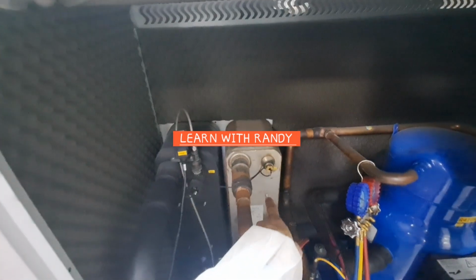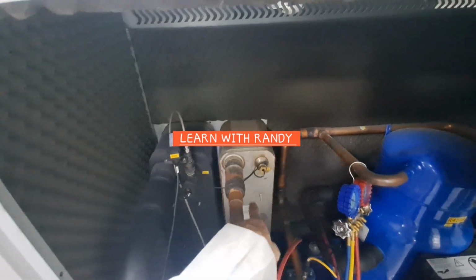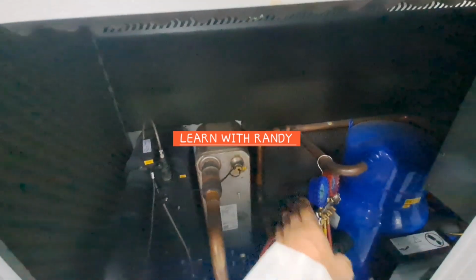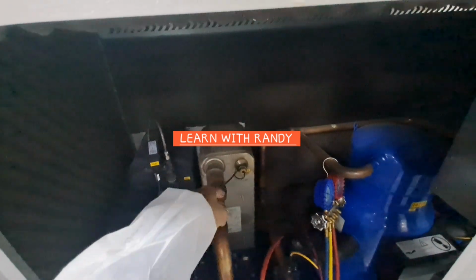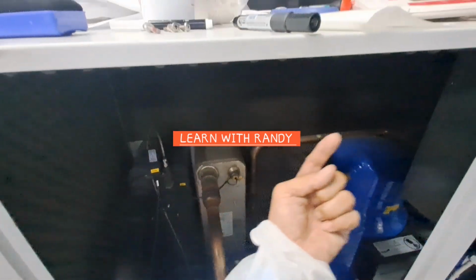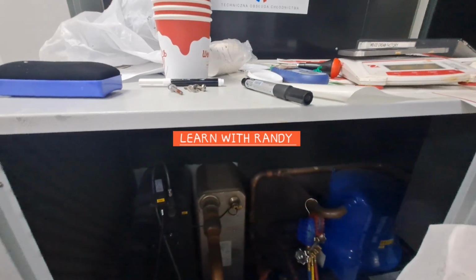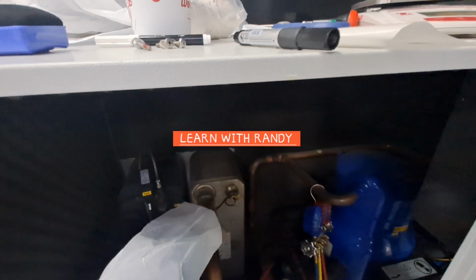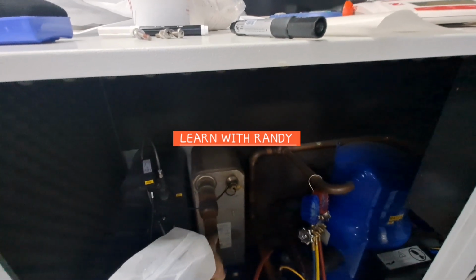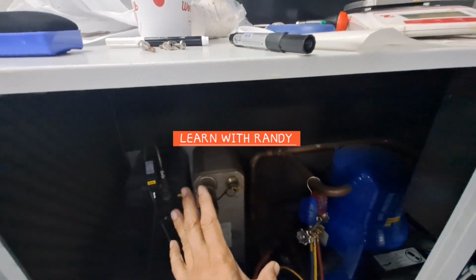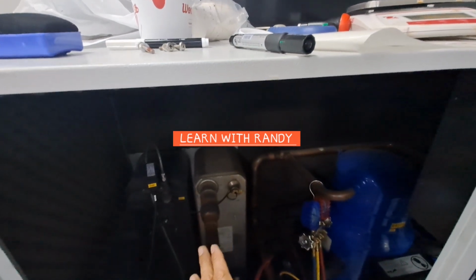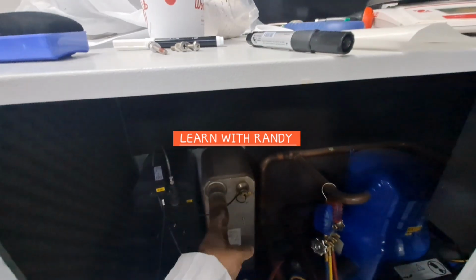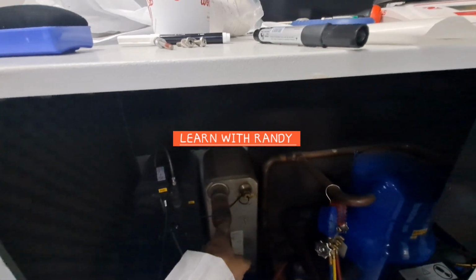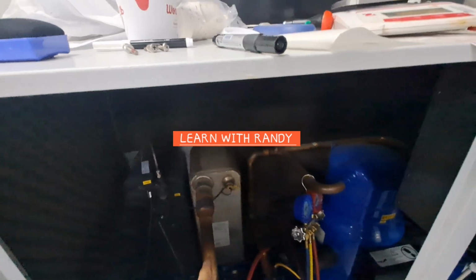And this other heat exchanger is for the discharge. So basically the hot gas, when it flows here, will cool down because there is water circulating here, going out to the cooling tower. The cooling tower will cool down the hot water, and that water becomes cold and will pass through this heat exchanger. So this heat exchanger acts like an external condenser. Rather than a condenser, this design uses a heat exchanger. So the water is passing through the heat exchanger, and it is being cooled down by the cooling tower.